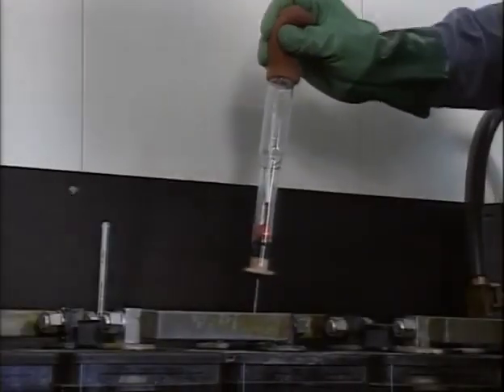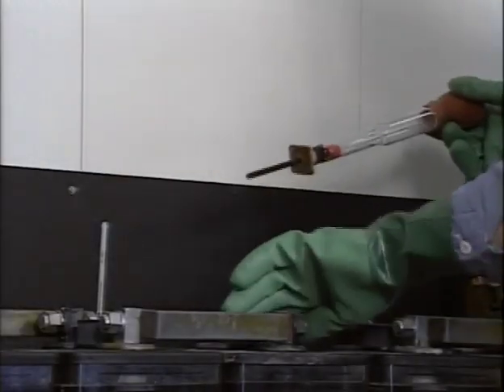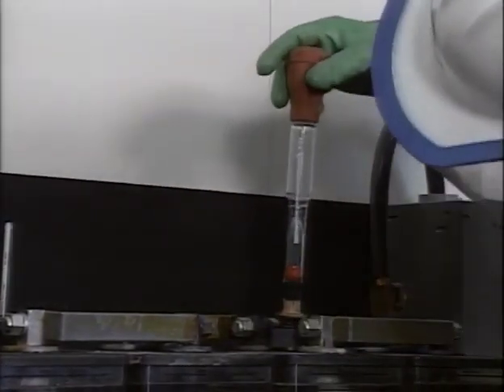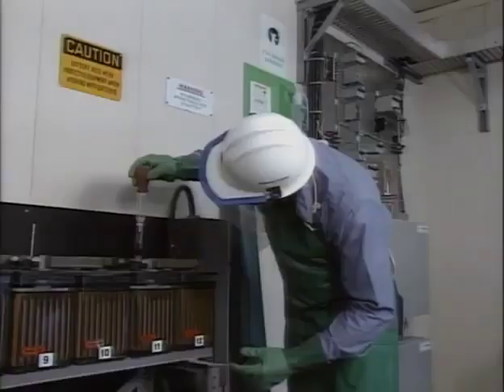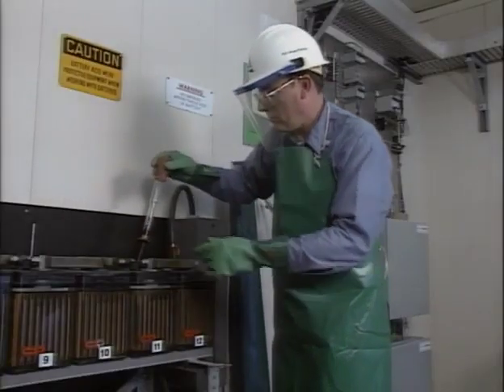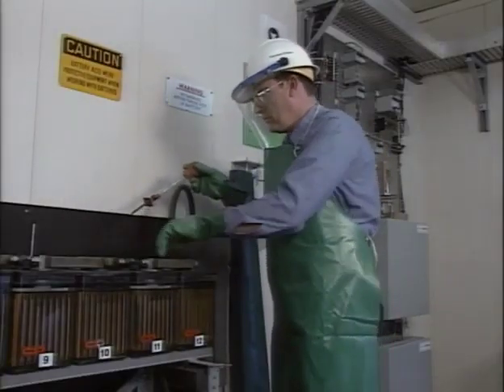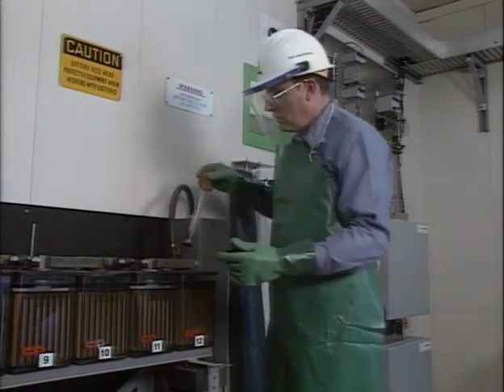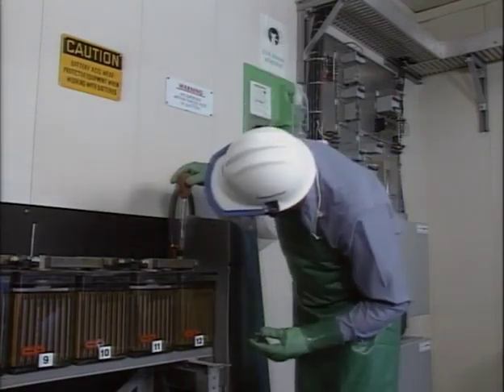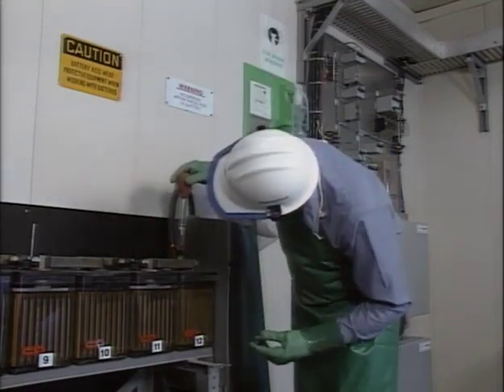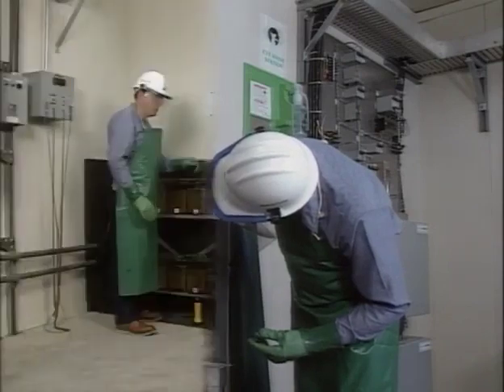After the specific gravity reading is taken, the electrolyte is returned to the same cell from which it was taken, and the specific gravity of the next cell can be taken. As with voltage testing, IEEE Standard 450 recommends checking pilot cell specific gravity once a month, and all cell specific gravities at least once per quarter.